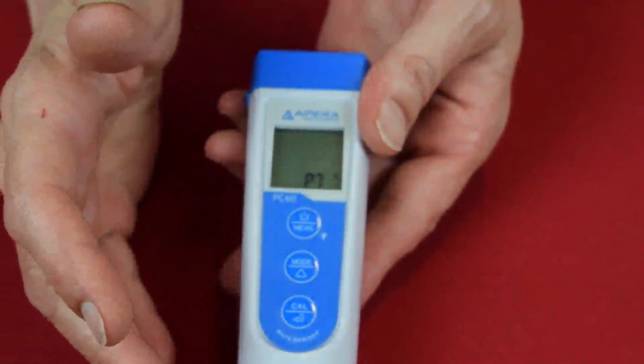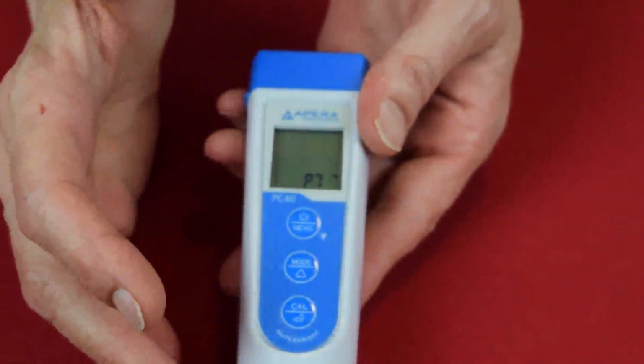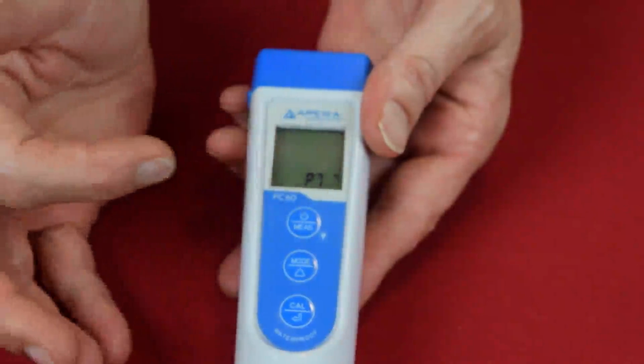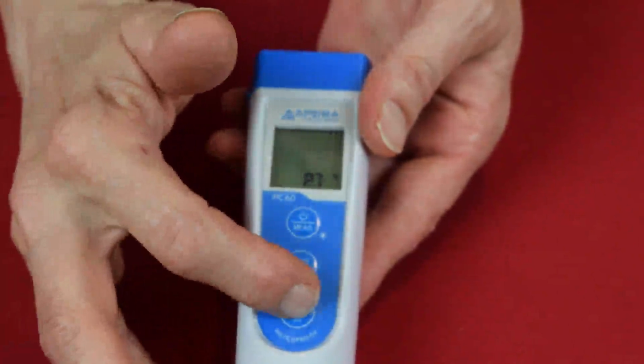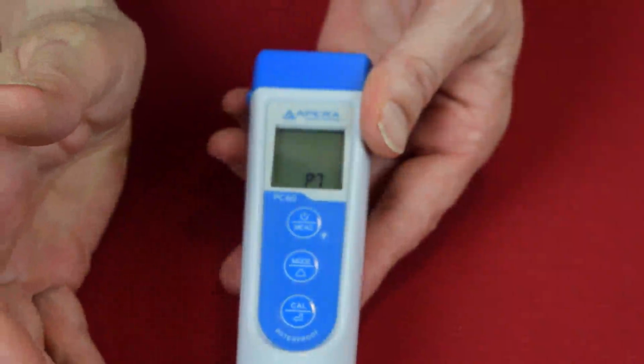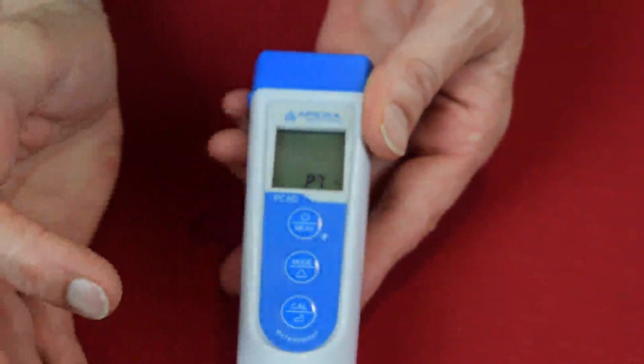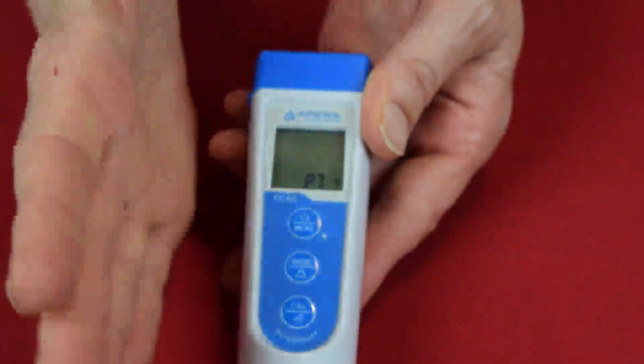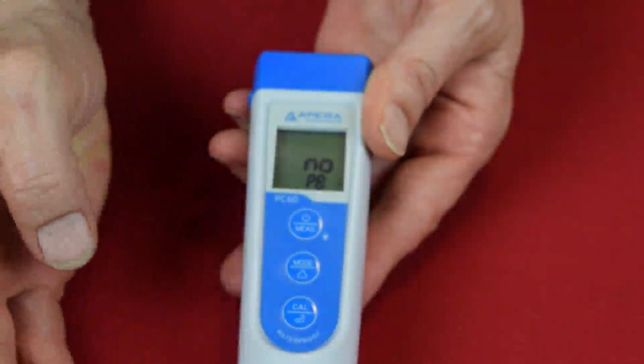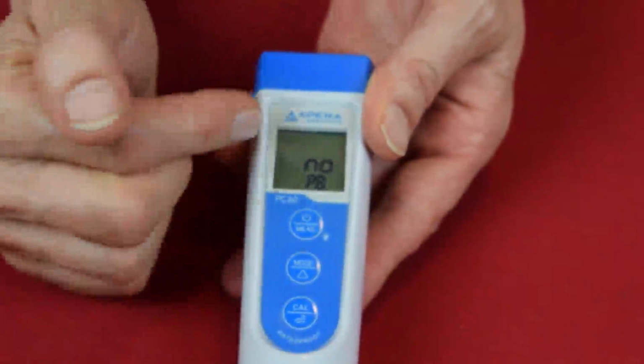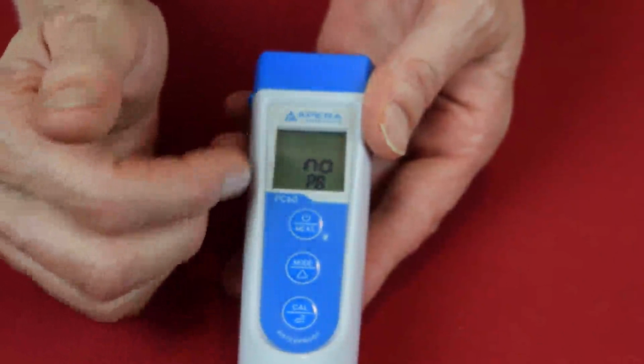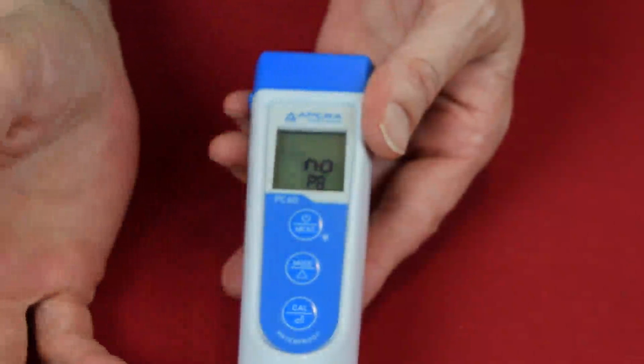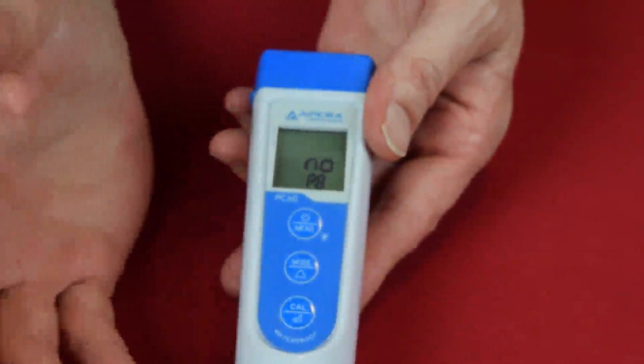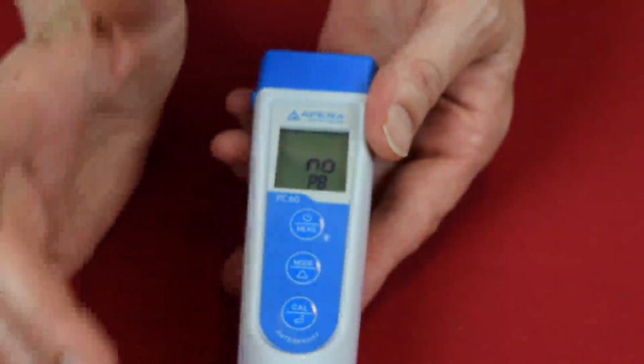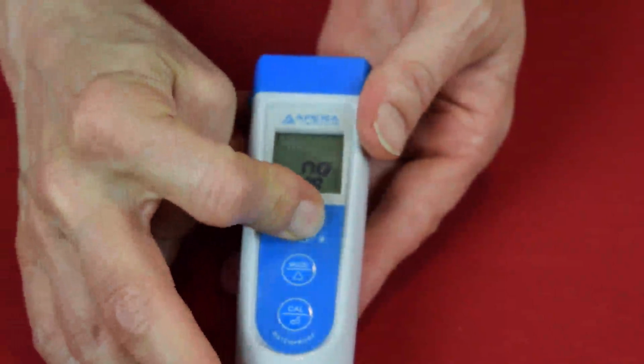And then P7 allows you to select the temperature unit, whether you want centigrade or Fahrenheit. I am in centigrade now, so I'm going to change that to Fahrenheit. I'm going to hit the cal button and then press mode to go to Fahrenheit, and then press cal to lock that in place. And then the next one we go to is P8, and that is to set it back to factory defaults. And it's no or yes. So if your computer messes up or something, it's not working right, you reboot it. This is basically rebooting this thing. So I'm going to go ahead and shut this thing off.